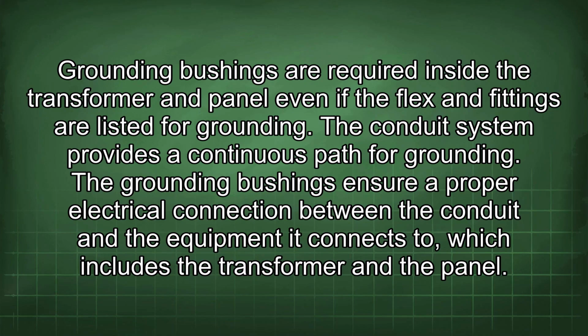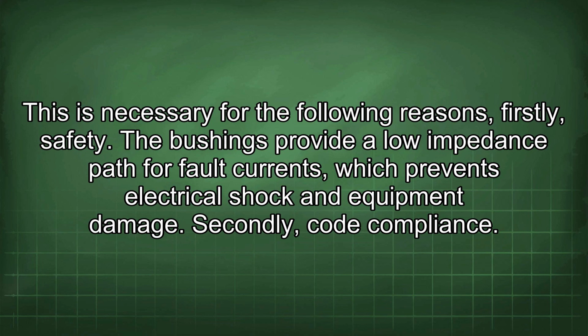Grounding bushings are required inside the transformer and panel even if the flex and fittings are listed for grounding. The conduit system provides a continuous path for grounding. The grounding bushings ensure a proper electrical connection between the conduit and the equipment it connects to, which includes the transformer and the panel. This is necessary for the following reasons.